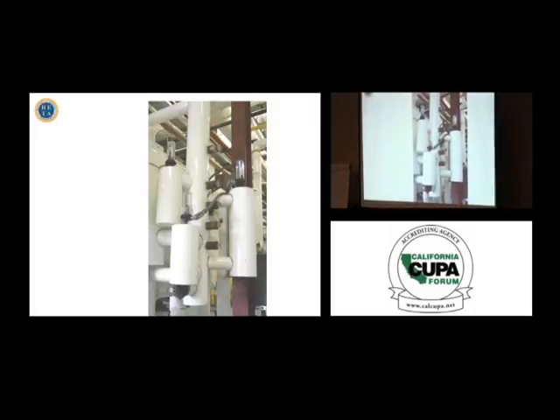You know, three level switches here. This one will shut off the machine if it gets too high. This one says, I want to have at least this much. This one here is to protect the pump. If it goes too low, I'll cavitate the pump. I'll have a seal problem. So again, same part number, different functions, but all have to do with the needs of the system.